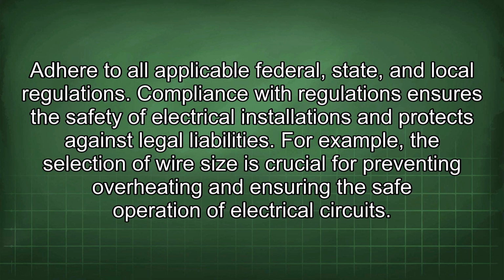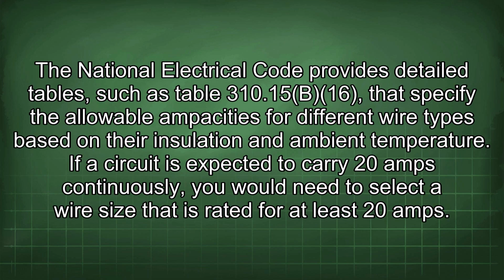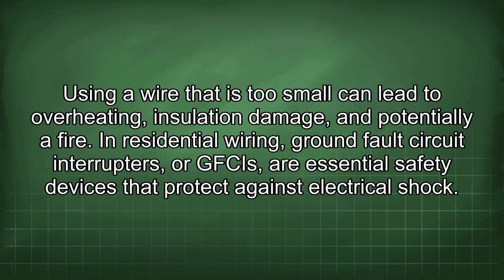For example, the selection of wire size is crucial for preventing overheating and ensuring the safe operation of electrical circuits. The National Electrical Code provides detailed tables, such as Table 310.15(B)(16), that specify the allowable ampacities for different wire types based on their insulation and ambient temperature. If a circuit is expected to carry 20 amps continuously, you would need to select a wire size that is rated for at least 20 amps. Using a wire that is too small can lead to overheating, insulation damage, and potentially a fire.